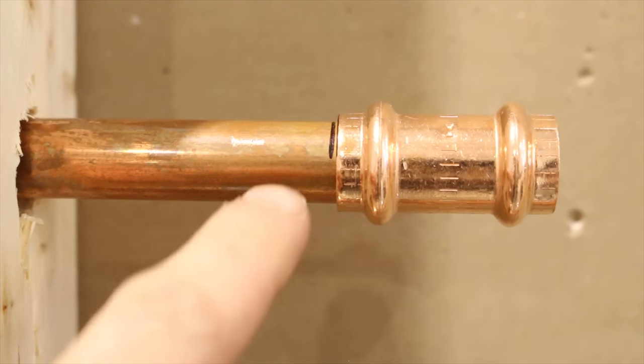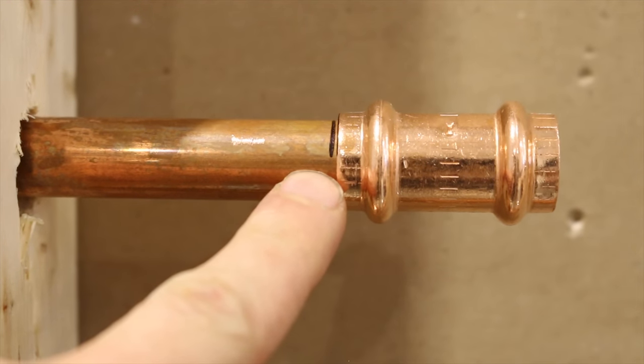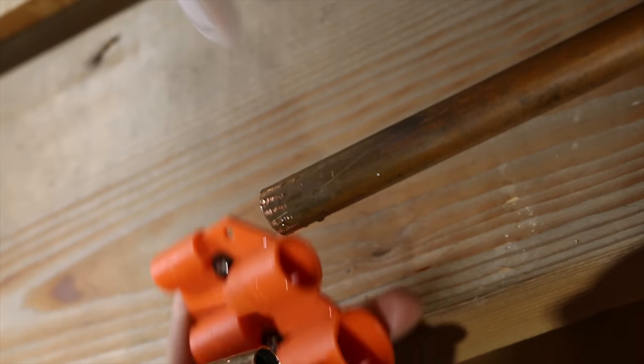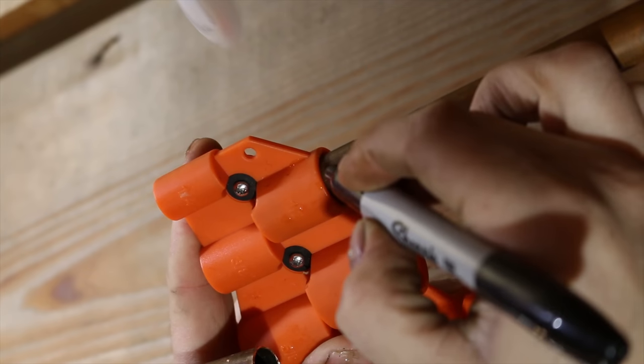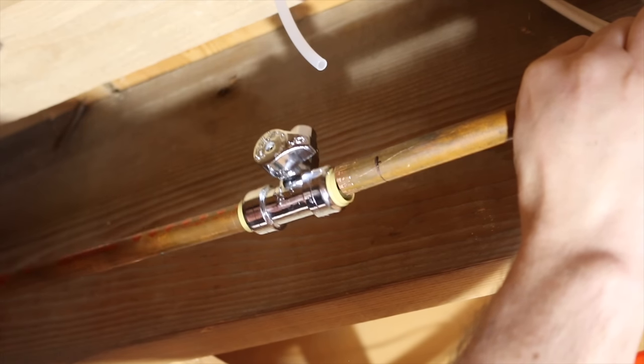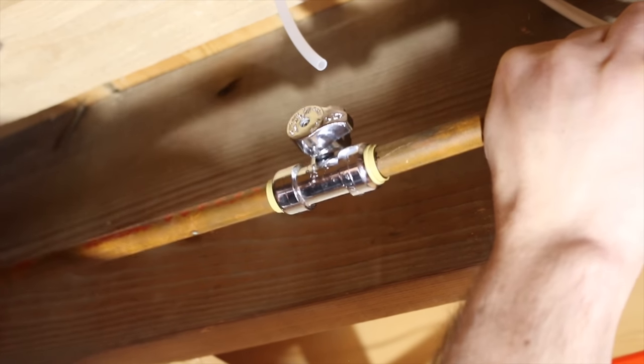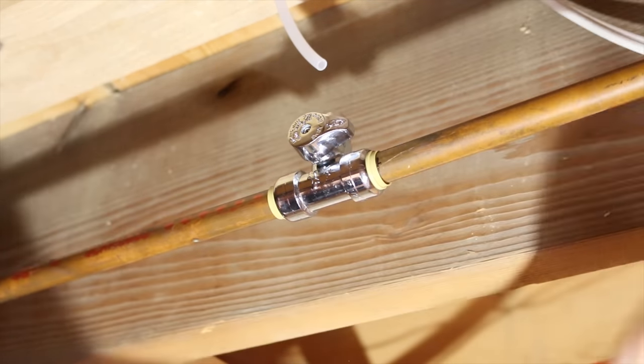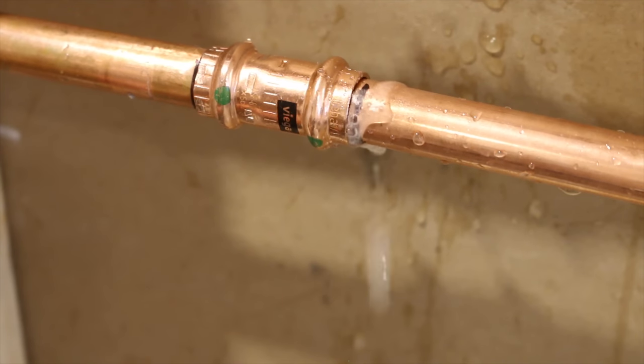Number nine is not making a reference mark when installing ProPress or SharkBite fittings. Whenever installing any fitting with a gasket such as a push fitting or ProPress fittings, it's super important to make a reference mark to know if the fitting is in all the way. A lot of installers will skip this step and get leaks once the pressure's back in because the fitting wasn't pushed in all the way.